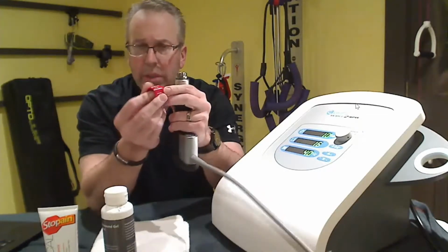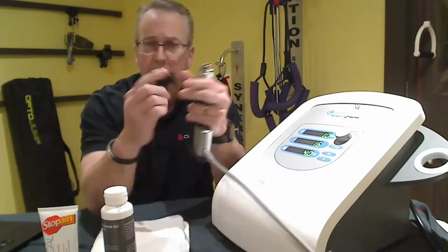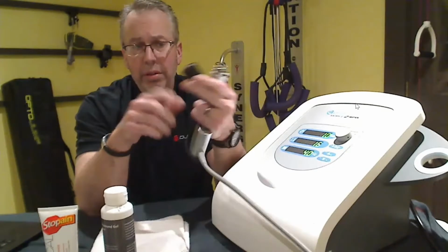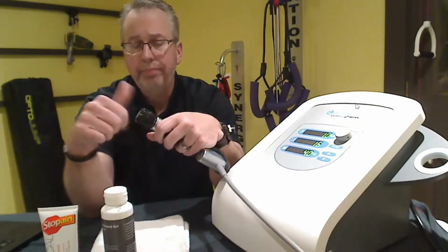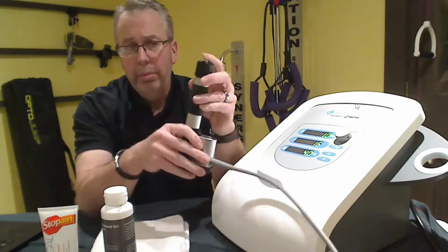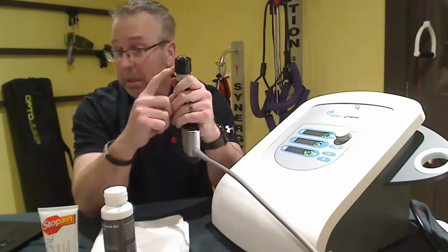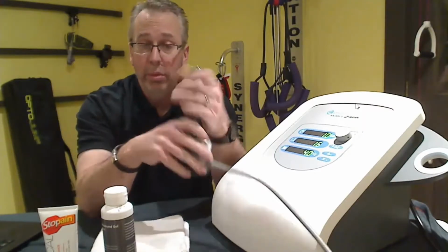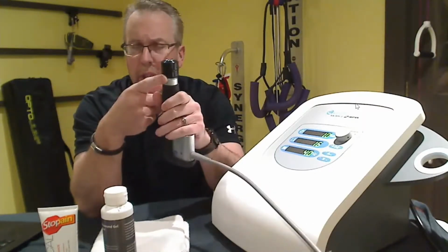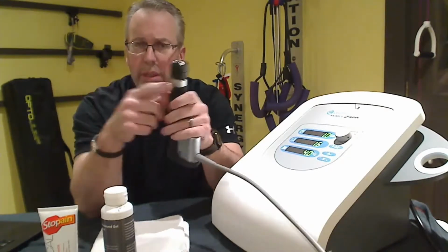That way we can control the concentration and the depth of penetration. Here's the D20S, the D20 standard. It's a broader head and has a greater depth of penetration. This is also made in titanium, which has even greater depth of penetration and more concentration of energy. So we consider what depth of penetration we're going to be doing with it, and that's how we determine the heads.